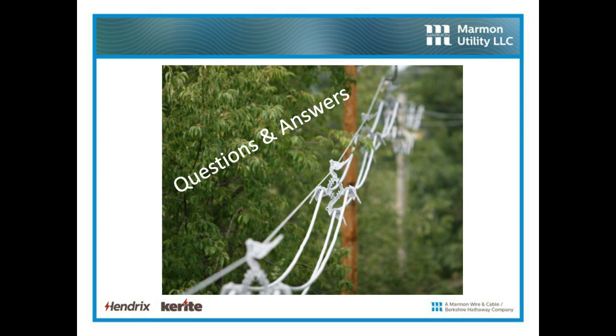Then I put my phase conductors at the payout pole into my dead end grips. Now I'm completely dead ended. Now I just roll down the street in the bucket truck and take off the roll-by block every 30 feet and replace it with a spacer until I've reached the far end. Okay, great. We have installation instructions that spell this out, and also a complete service department of installation specialists that regularly work with utility clients to get this done.